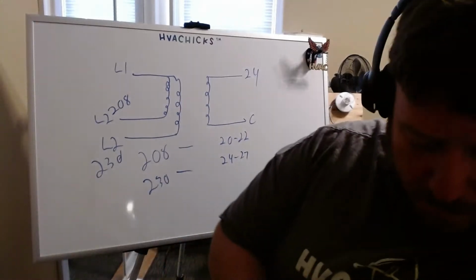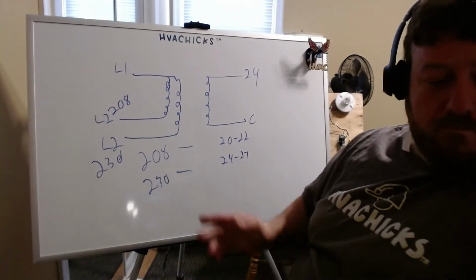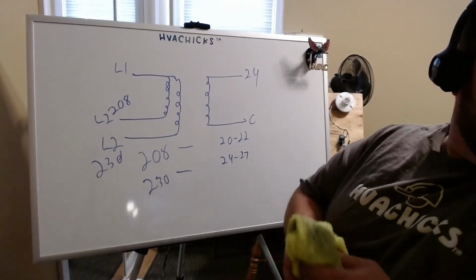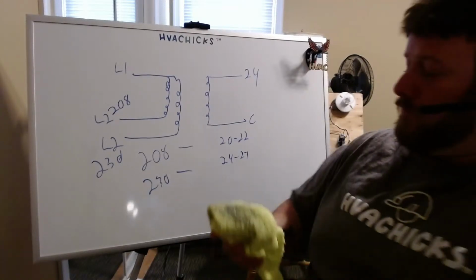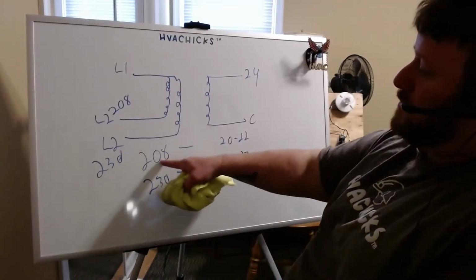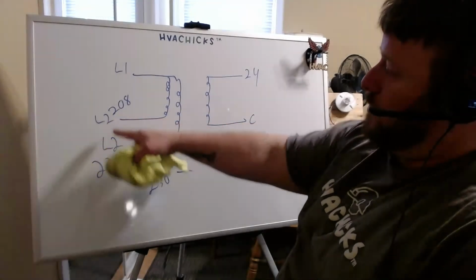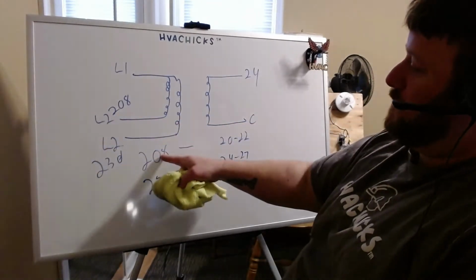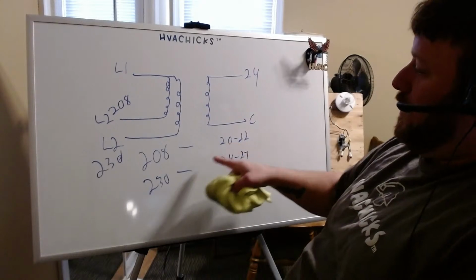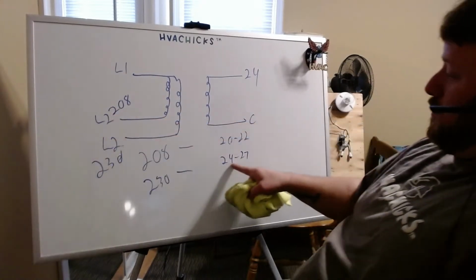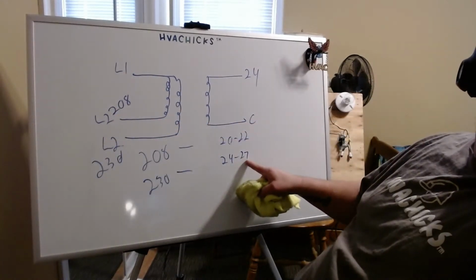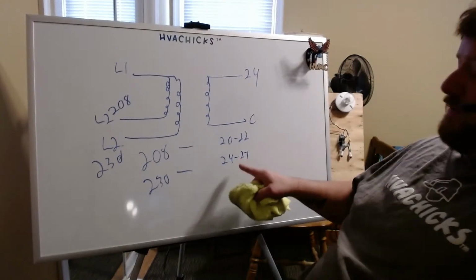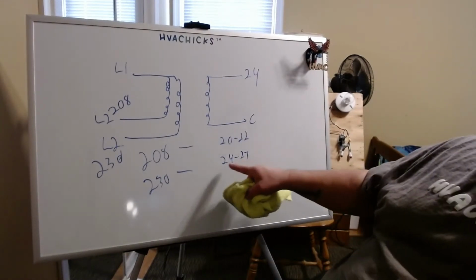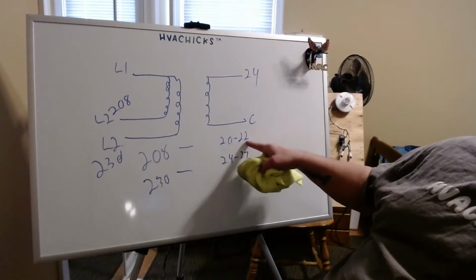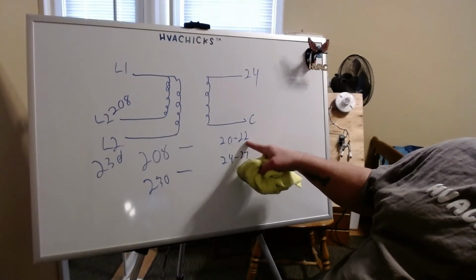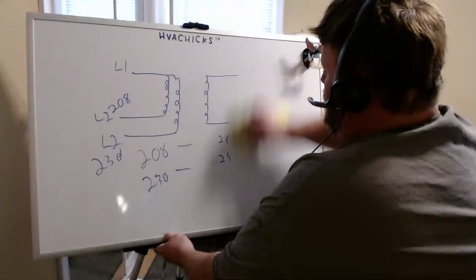And I'm gonna get to this wiring in here with the high voltage to explain that to you. So make sure if you're using 208 volt, your tap is on 208. Because if not, you'll get this low voltage. As soon as you move the tap over here to 208, you'll get your 24 to 27 volts. Okay. This is crucial because everything being so electricity sensitive now, this will throw off your system and cause you to mess up contactors and relays.